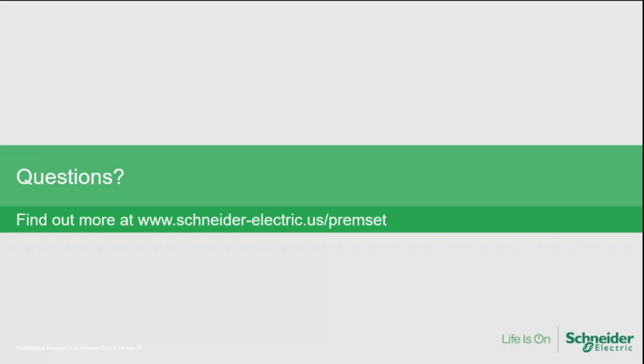So, good question there. What is the recommended test period for the metal enclosed switchgear? Annually. Yes, traditional metal enclosed switchgear is recommended by most manufacturers to be tested annually. Some manufacturers, I think, have a 3-year recommendation in their O&M manuals. But again, generally 1 to 3 years is the recommended interval. Now, that being said, you should always go off the recommendations of the manufacturer of the switchgear that you have. So I would encourage you to check that in the O&M manuals for whatever manufacturer of switchgear you do have.